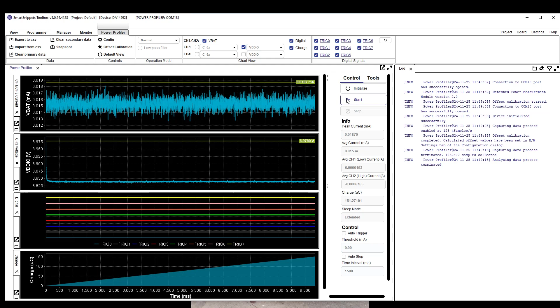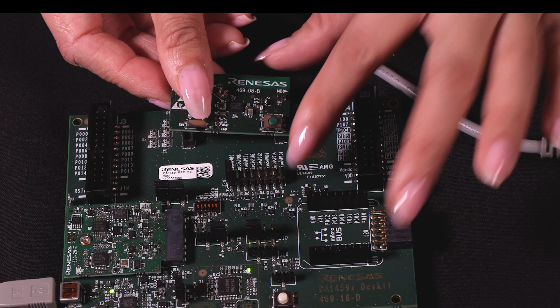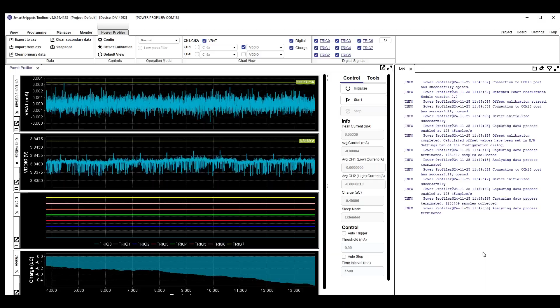Please note that at the time of the samples being collected, none of the buttons are selectable. They're all grayed out. Once all the buttons are selectable again, press Start. Check the value displayed on the average current field. This is the current introduced by the motherboard that we would like to subtract from subsequent measurements. The average current is multiplied by -1 and set as the calibration offset in the Power Profiler configuration. This negative offset is expected because for PMM1, the offset is added to the measured current, so using a negative value corrects the measurement. And now we can finally connect, or alternatively, switch on the daughter board and follow the normal procedure for taking measurements.